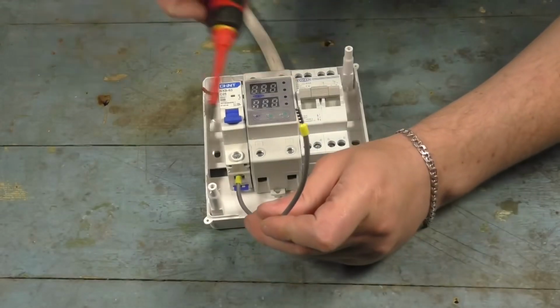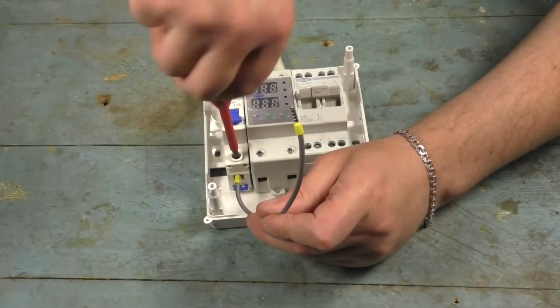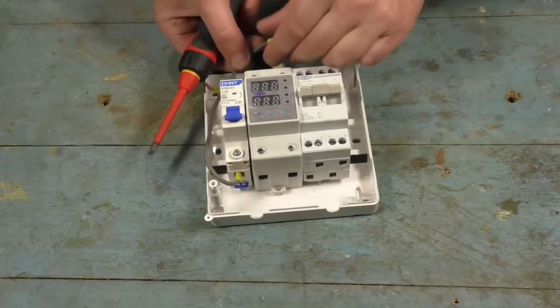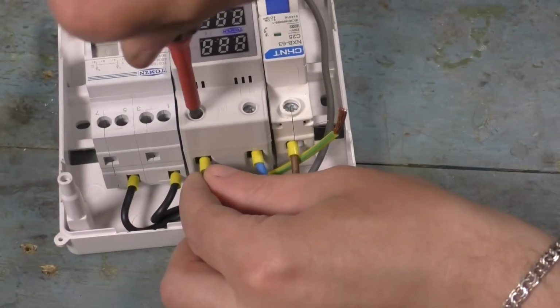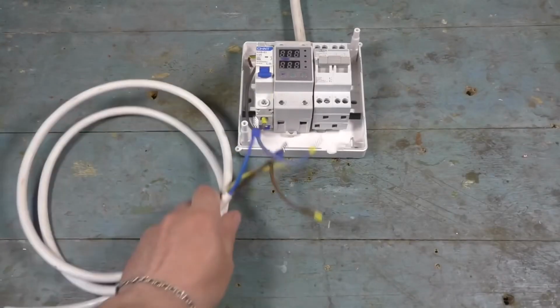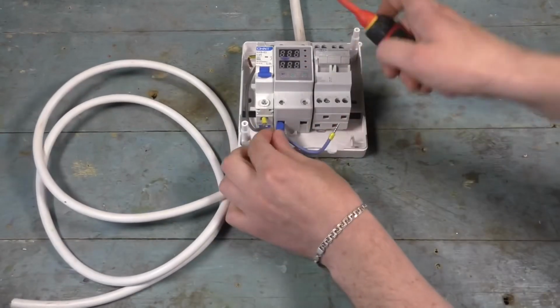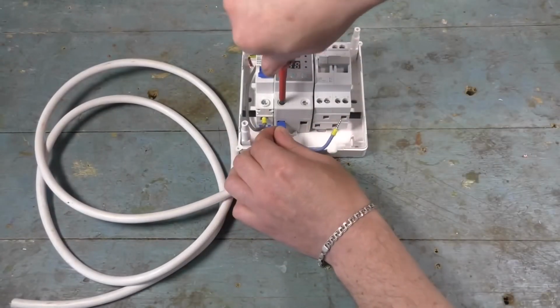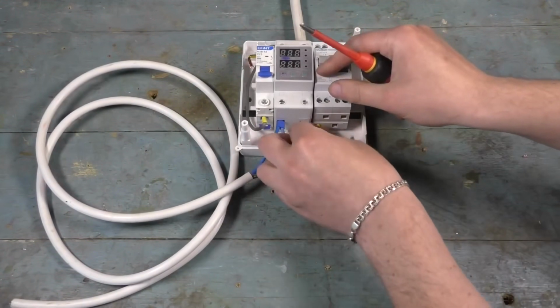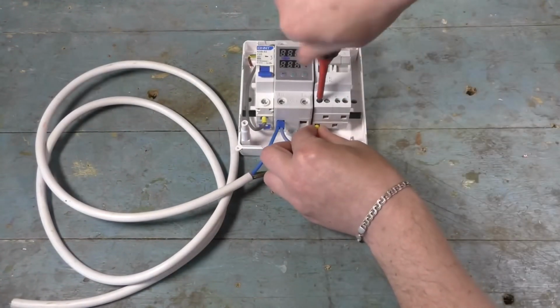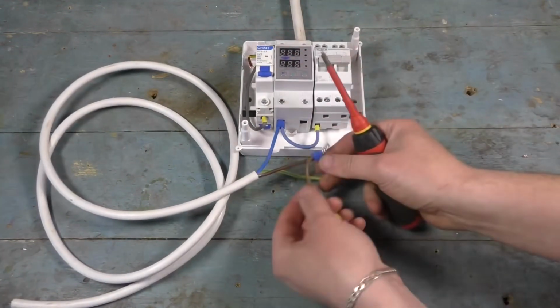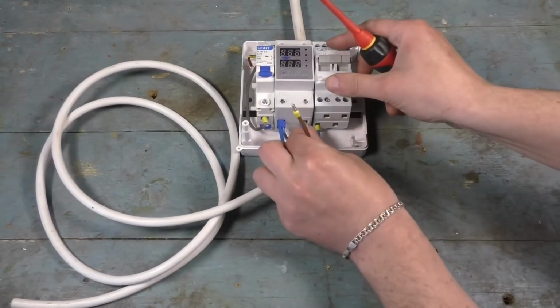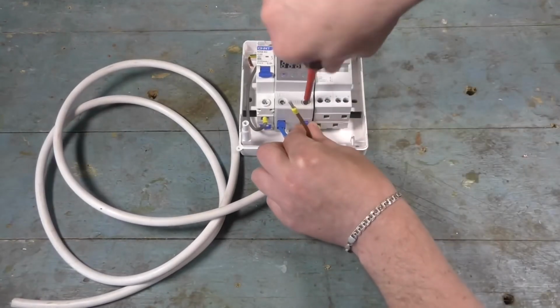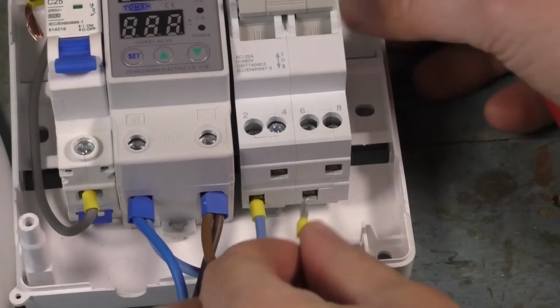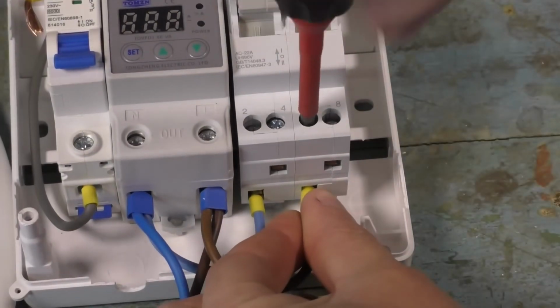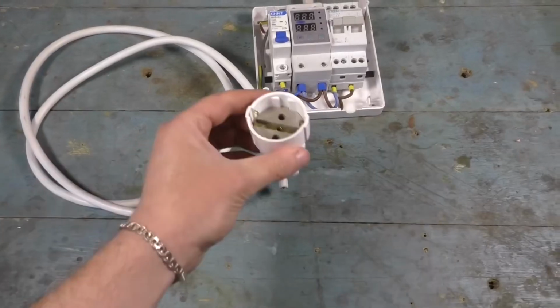A jumper is installed at the output of the circuit breaker and connected to the input of the voltage relay at terminal L. Next, you will need a cable with a cross-section of 2.5 square millimeters. The brown and blue wires are connected directly to the jumper. The blue wire is connected to the output of the voltage relay at terminal N, and its jumper is connected to terminal 2. The brown wire is connected to the output of the voltage relay at terminal L, and its jumper goes to terminal number 6. You need to connect a socket to the opposite end of this cable.